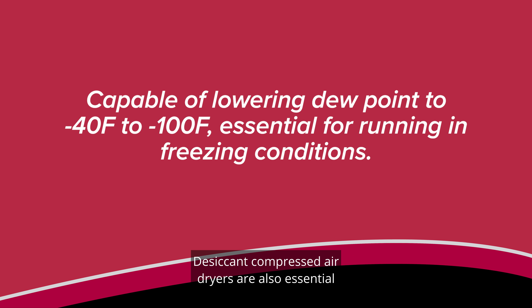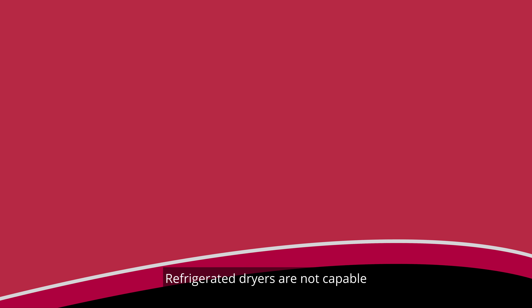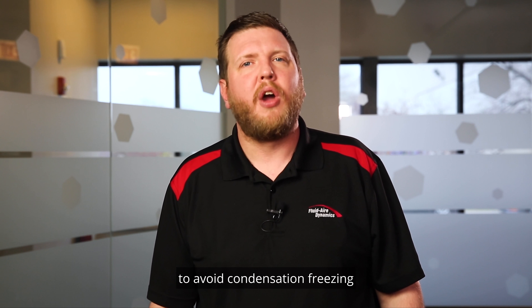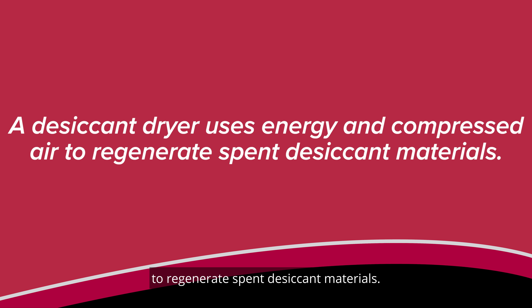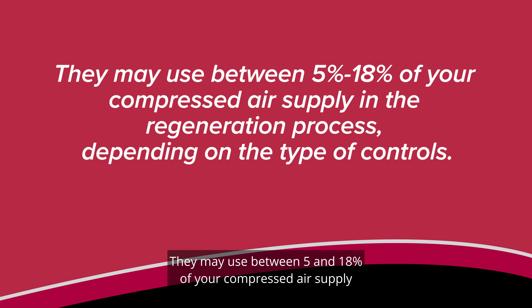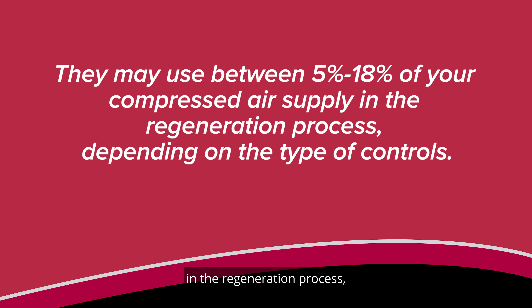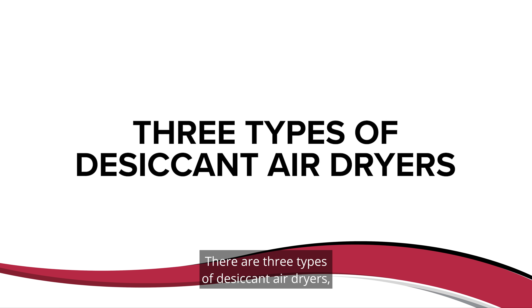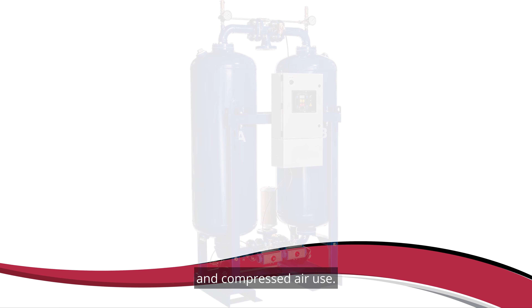Desiccant compressed air dryers are also essential if your applications run in freezing conditions. Refrigerated dryers are not capable of reducing the dew point low enough to avoid condensation freezing when operating at very low temperatures. A desiccant dryer uses energy and compressed air to regenerate spent desiccant materials. They may use between 5 and 18 percent of your compressed air supply in the regeneration process, depending on the type of controls. There are three types of desiccant air dryers which vary in the regeneration methods, energy cost, and compressed air use.